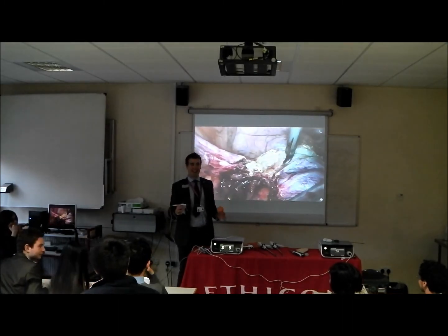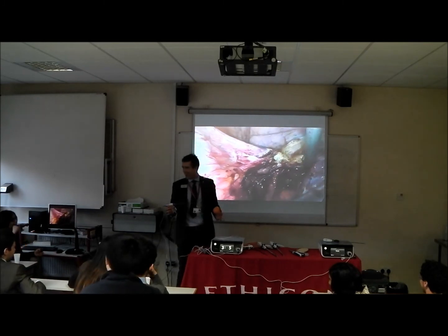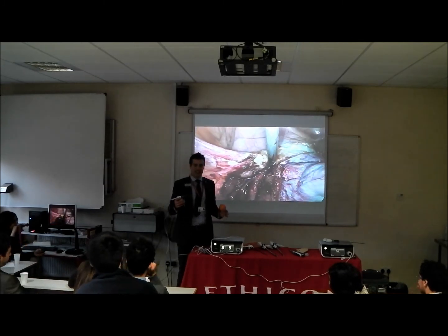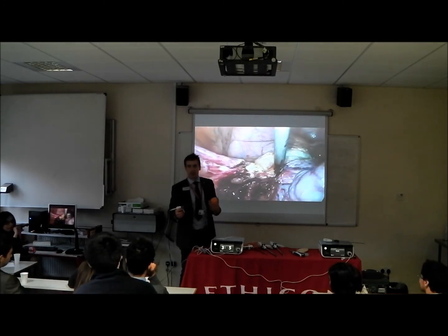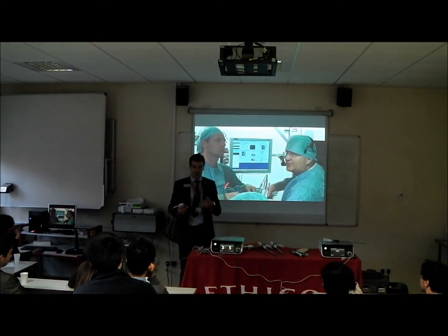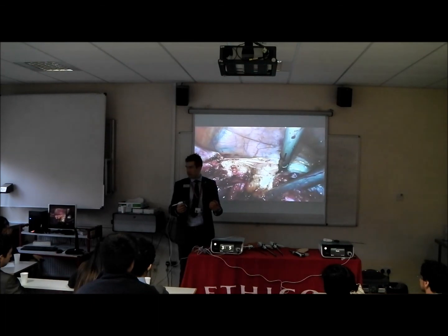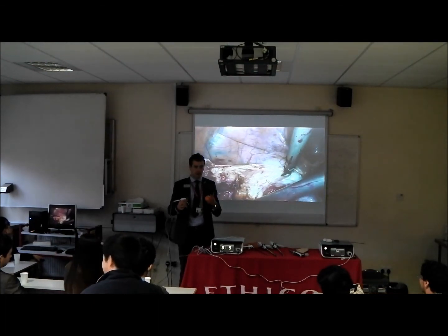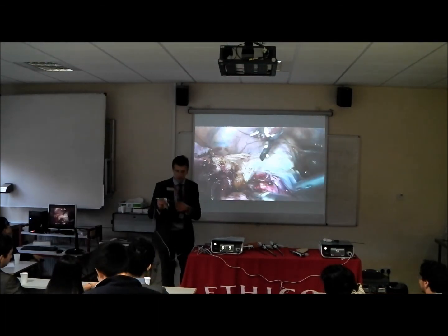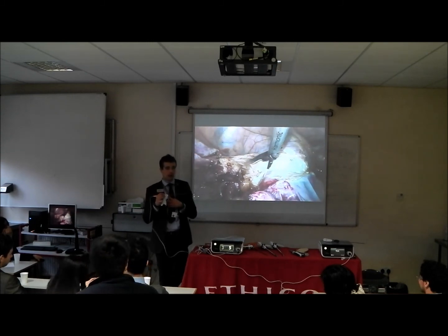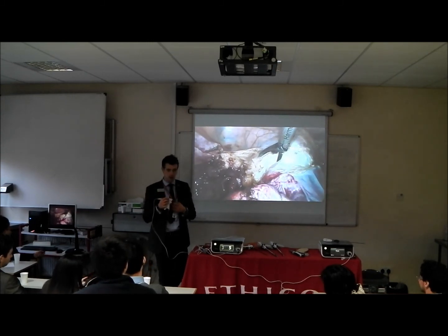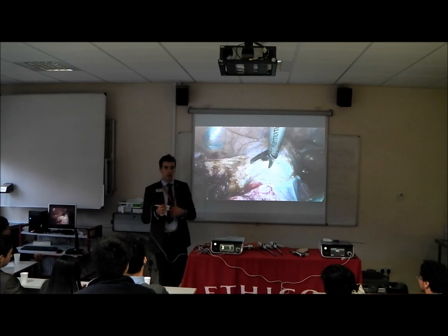Just before we pile in, although it's mechanical energy and it's not electricity that's going through to the patient, the jaws of the device will get extremely hot. It'll be about 100 degrees, I think, so don't touch the end of the device. There are 2 different settings. If you press the maximum button, that will cut, and you'll hear the loud tone. If you press the minimum button, that will coagulate.